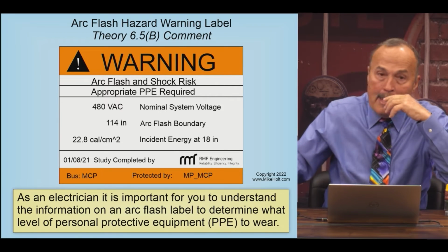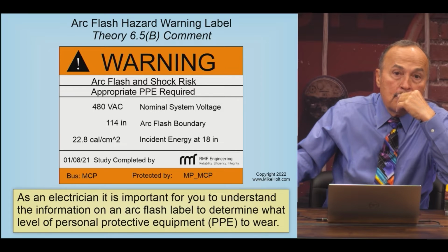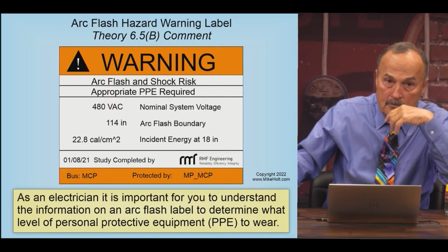Brian made a comment: saying 1.2 calories is okay isn't a great way to put it, because while 1.2 calories might be fine if your skin's exposed, there are still risks if you're wearing improper or contaminated clothing, since that clothing could catch fire at 1.2 calories. So you can't just say 1.2 calories is okay, there's still a risk, you always want to be wearing FR clothing in that scenario.